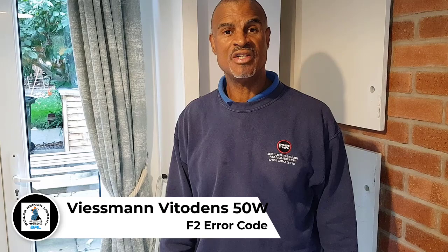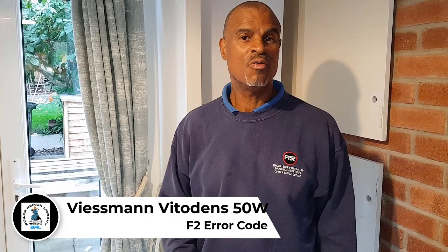Hi guys, it's Master Coach Tony Marken and today's video is on the Viessmann Vitodens 50W. We've got a bit of a story to tell you before we get involved with the video. Yesterday I was here and the customer said they had an F1 code. F1 means the fluid sensors are overheated or going to high temperature.